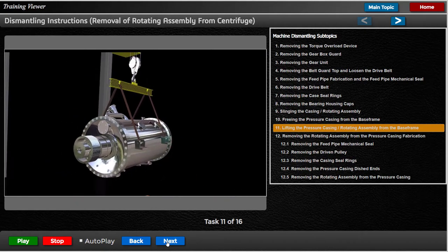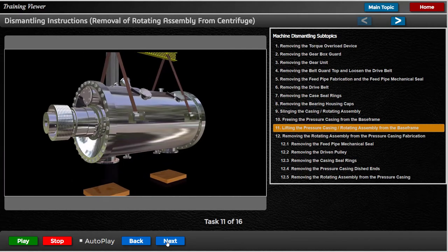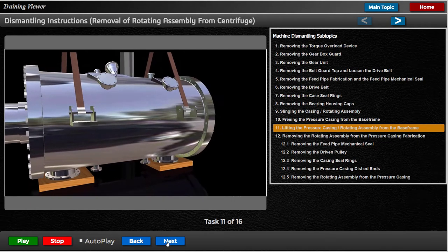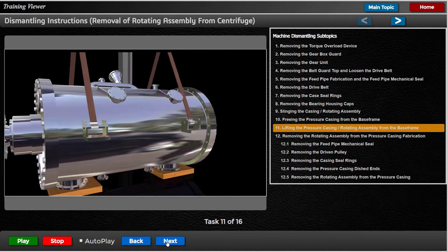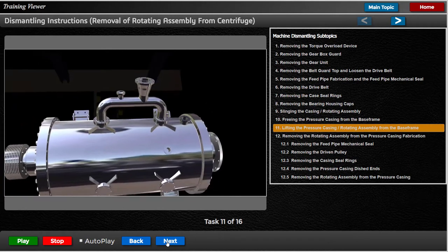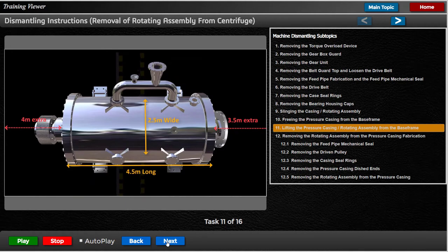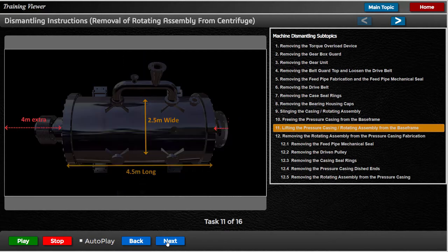Once the assembly is lifted clear and taken to the work area, it should be lowered down and rested on the discharge hopper mounting flanges. Place the casing on 1200 x 500 x 100 mm thick wooden planks. This is both to protect the flanges and to aid in the removal of the rotating assembly from the pressure casing. The minimum work area required is 4.5 meters long and 2.5 meters wide, with extensions in length for withdrawing the rotating assembly of 3.5 meters at the solid end and 4 meters at the feed end.